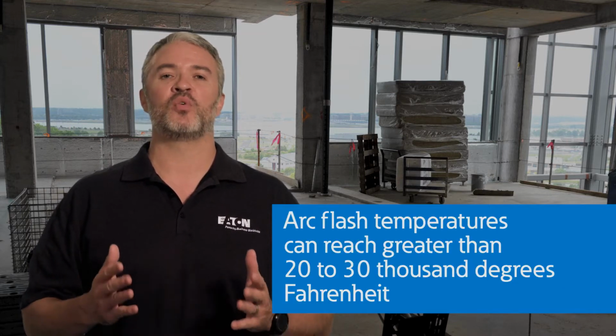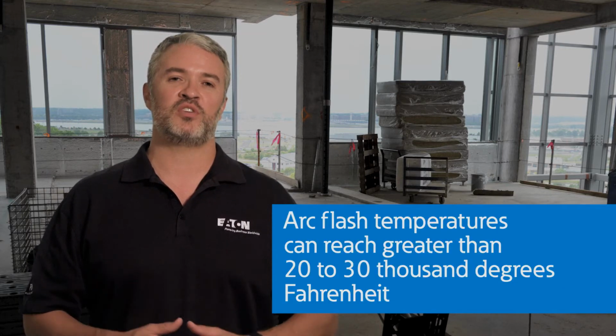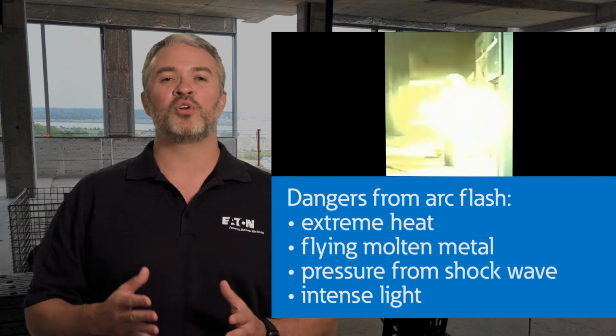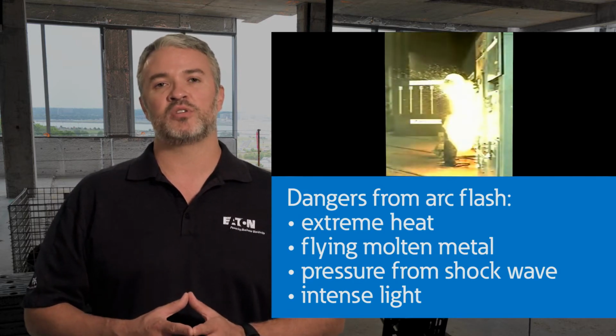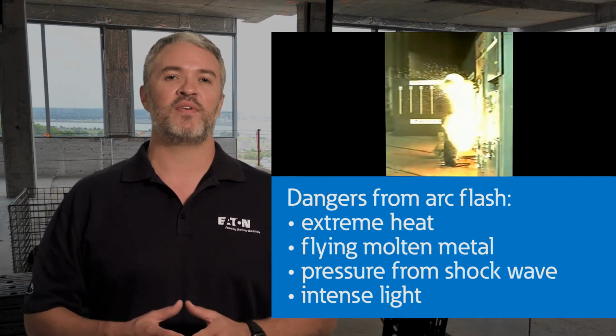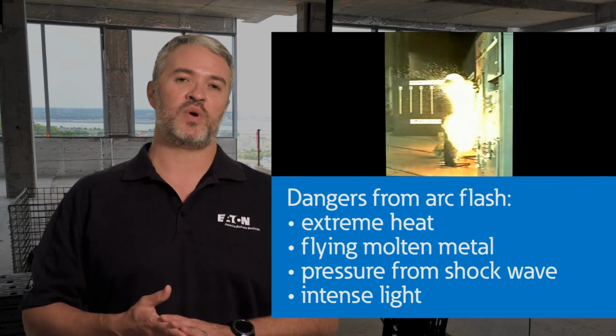What are the key things for you to know about arc flash hazards as it relates to you in hospital applications? The release of energy caused by an arc flash can reach temperatures that are greater than 20 to 30,000 degrees Fahrenheit. This release of energy is dangerous in many ways, including the extreme heat, flying molten copper that gets vaporized at these temperatures, the pressure from the shock wave, and the high levels of light from the radiation wave.